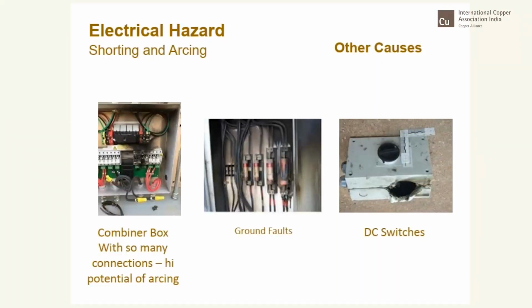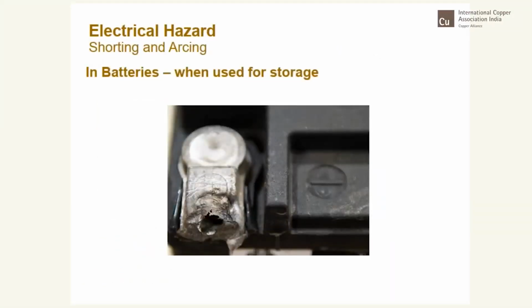And then you see the ground faults causing the fuse to blow, and then DC switches again, because it was not able to withstand the breaking temperature, the flame that was coming, so it has got burnt. And then electrical batteries, of course, if you are using them and they are shorted or a large current is drawn beyond the rated capacity, then that can also cause fire accidents.